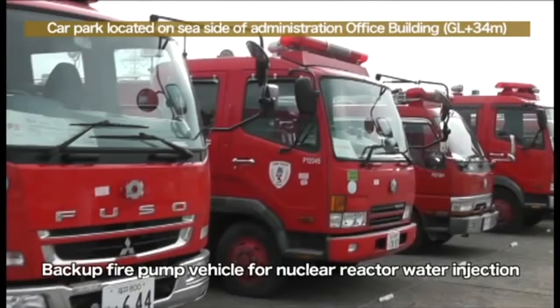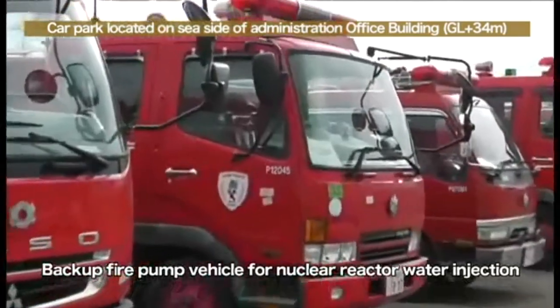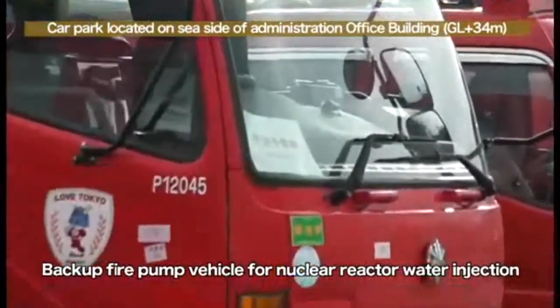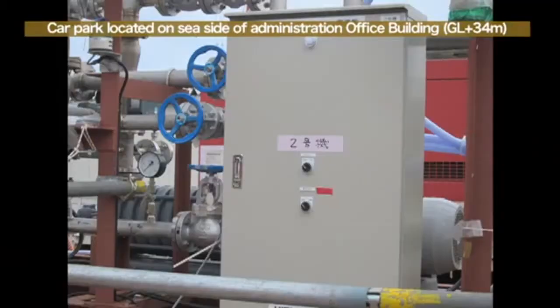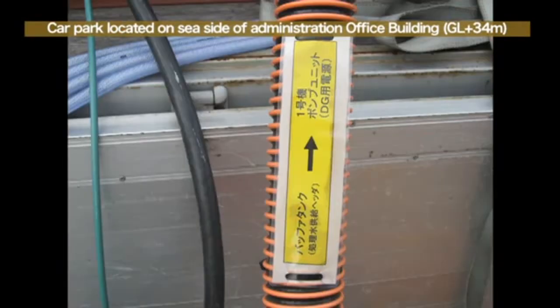On the hill, there are 3 pumps for regular use and 3 pumps for emergency use. In the event that all pumps malfunction, we have prepared 3 fire trucks for backup, which are already refueled and at the ready. GL plus 34 meters on the upper left of the screen means that the pumps and the fire truck are situated 34 meters above sea level. They cannot be damaged even if a huge tsunami occurs. If necessary, we will affix marks on the hose pipes in order to help us understand where each hose pipe is attached.